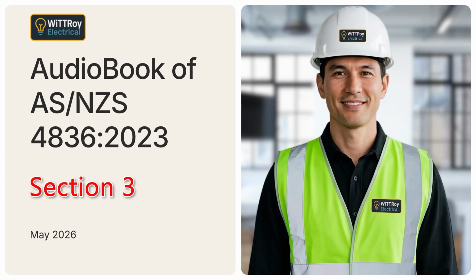An isolating transformer must comply with the AS/NZS 61558 series. An RCD must be Type 2 30 mA or comply with AS/NZS 61008.1 or AS/NZS 61009.1. The simple message is that plug-in electrical equipment can still present serious shock risk during energized testing. Extra protection should be used where energized fault finding or testing is required.